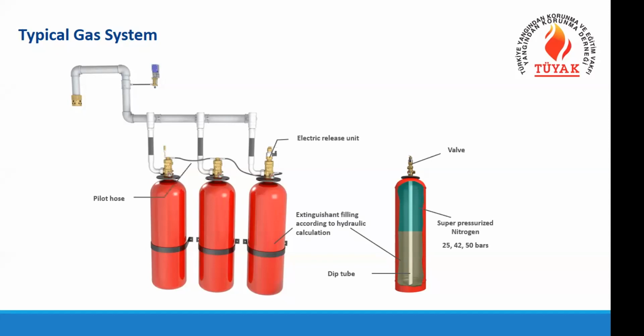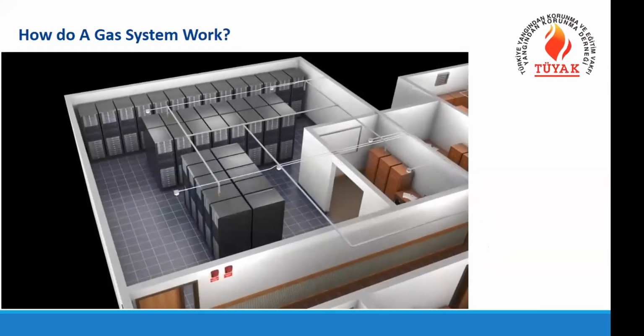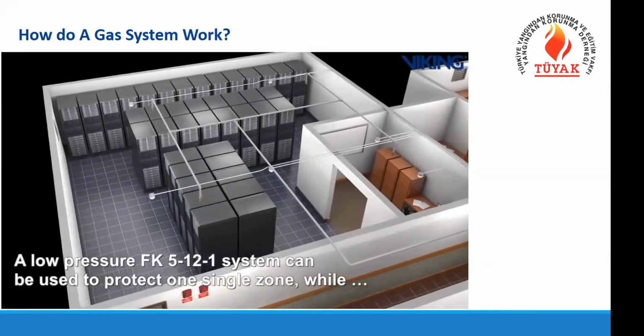And there is an electric release unit. When detectors come, it gives a signal to the panel. The electric release unit is energized by the control panel, and the system activates and the gas is discharged. We still need a detection system here to operate this system. Let's see how a gas system works.